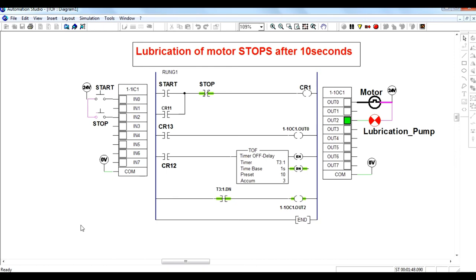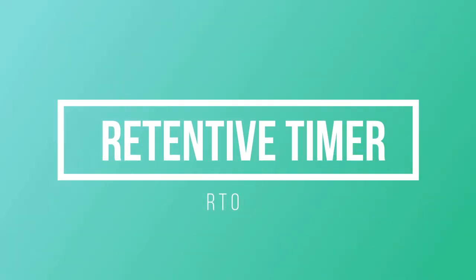The next type of timer is the retentive timer. The application of this timer is: whenever you stop the system, the time for which the machine has run is not lost as with other timer types. The retentive timer starts counting from where you stopped the system. In this ladder diagram, a motor and indicator are used. The preset value is set to 45 seconds and the time base is 1 second.